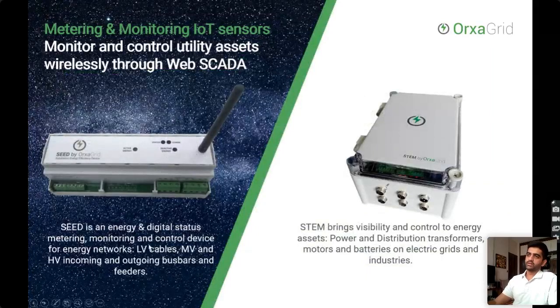So this is the seed device for feeder monitoring, and then taking the same unit and expanding its capabilities, we developed the STEM device, which is a transformer monitoring unit. STEM stands for Smart Transformer Efficiency Monitor, and the STEM is used for mainly monitoring of distribution and power transformers. It also has the same channel inputs of currents and voltages. It does the 1.6 kilohertz high-speed sampling of each phase, and it calculates all the metering parameters, from your energy, power factor, or frequency, and so on.